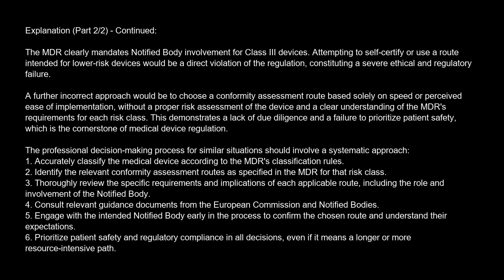The professional decision-making process for similar situations should involve a systematic approach. 1. Accurately classify the medical device according to the MDR's classification rules. 2. Identify the relevant conformity assessment routes as specified in the MDR for that risk class. 3. Thoroughly review the specific requirements and implications of each applicable route, including the role and involvement of the notified body. 4. Consult relevant guidance documents from the European Commission and notified bodies. 5. Engage with the intended notified body early in the process to confirm the chosen route and understand their expectations. 6. Prioritize patient safety and regulatory compliance in all decisions, even if it means a longer or more resource-intensive path.